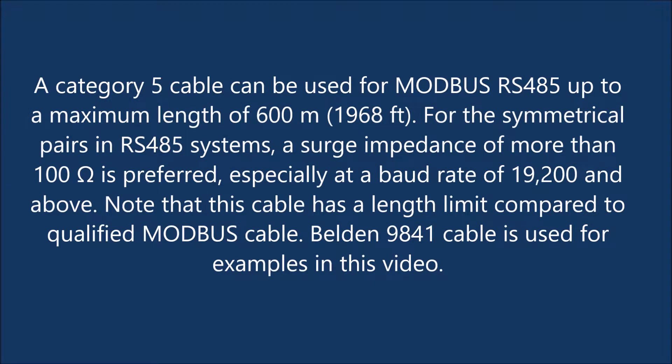A category 5 cable can be used for Modbus RS-485 up to a maximum length of 600 meters (1,968 feet). For the symmetrical pairs in RS-485 systems, a surge impedance of more than 100 ohms is preferred, especially at a baud rate of 19,200 and above. Note that this cable has a length limit compared to qualified Modbus cable.